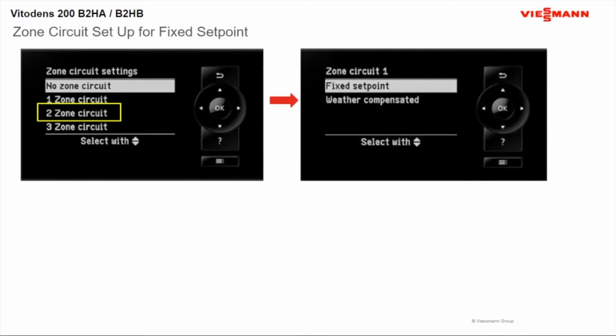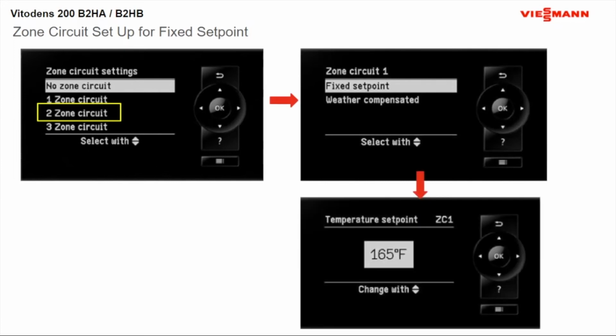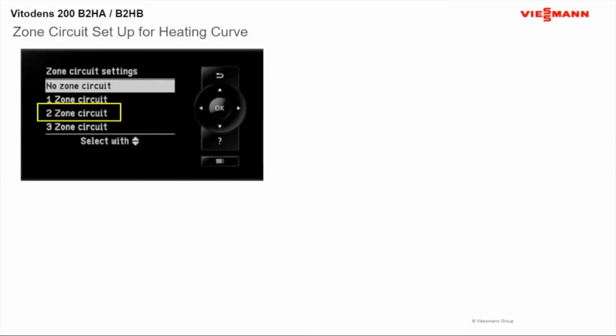For the first example, as you can see, as soon as we pick 2 zone circuits, we hit OK. The next thing it's going to ask you, do you want to do a fixed set point or do you want to do a weather compensating with heating curves? For this example, for zone circuit 1, we're going to pick a fixed set point. Hit OK. Next thing it's going to ask you is set your fixed set point. And this is pretty much where you're set to when you get the boiler. So when you get the boiler, if you want to hit those fixed set points, you're going to come here and put whatever temperature you want. If you want the 180 out of the boiler, you're going to hit your up arrow, make that 180, hit OK. Next thing it's going to ask you is, do you want to use a pump output? Remember those pumps I showed you at the bottom where we're going to wire those in, the 28/20 or the 157. Remember, we have to power that 157 output. So for this example, we'll pick the 28/20 output for the fixed set point. Click OK. That heating circuit 1 is now done.